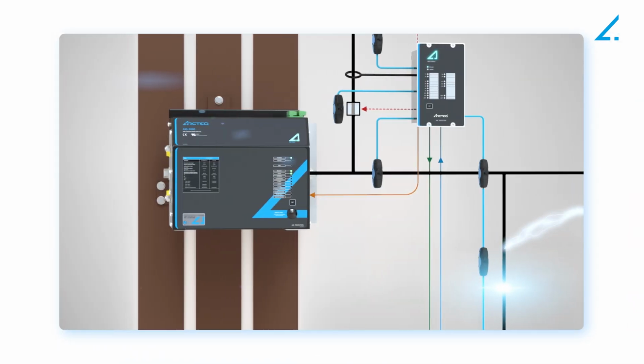Here you can see how the arc protection works. One of the sensors detects light at the outgoing feeder while the main device is measuring high current. The two criteria are fulfilled to trip both the circuit breaker and the arc quenching device. Arc flash current transfers to the quenching device, and the arc flash is extinguished in less than 4 milliseconds.